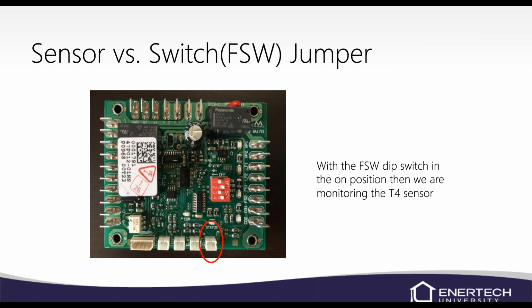Now, we have an FSW dip switch, which is the very top one, number one, and it will come in the on position from the factory. When it's in the on position, we're monitoring one of these bottom thermistors. We have 4 thermistors. If you look really close at this picture, you'll see LCT, DGT, DLWT, and SCT. LCT is load coil temperature. DGT is discharge gas temperature. DLWT is the domestic water line temperature. And SCT is source coax temperature.